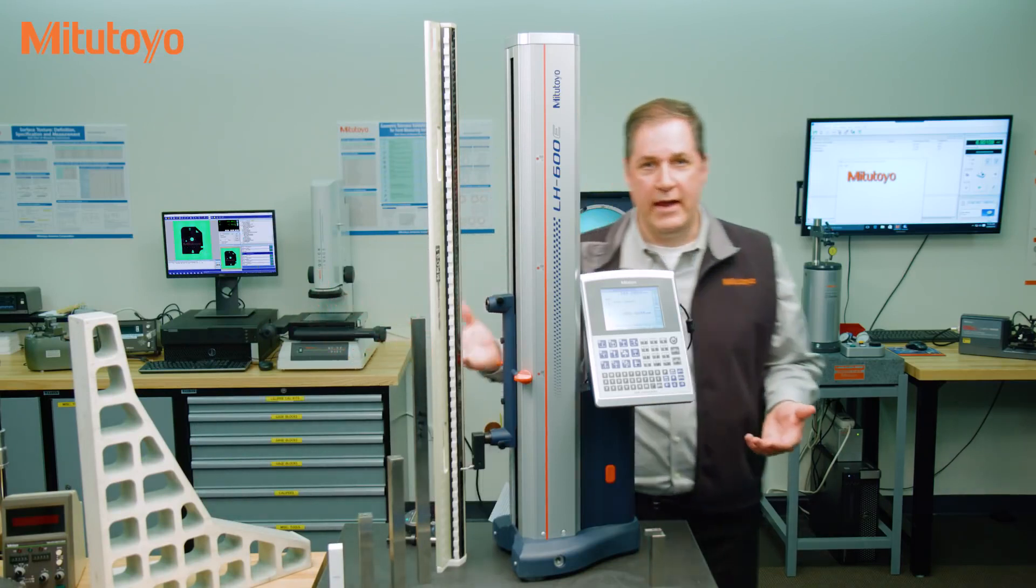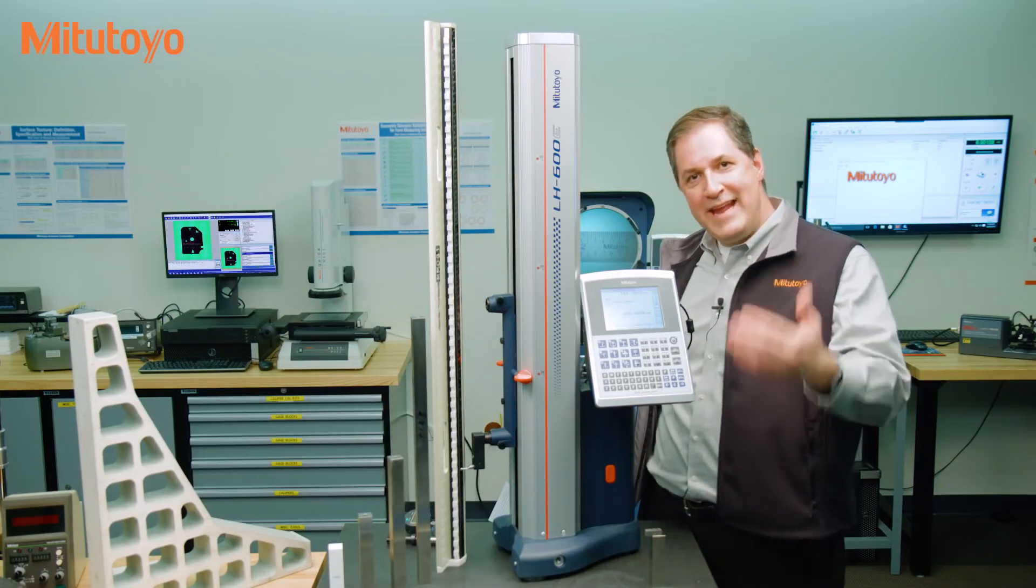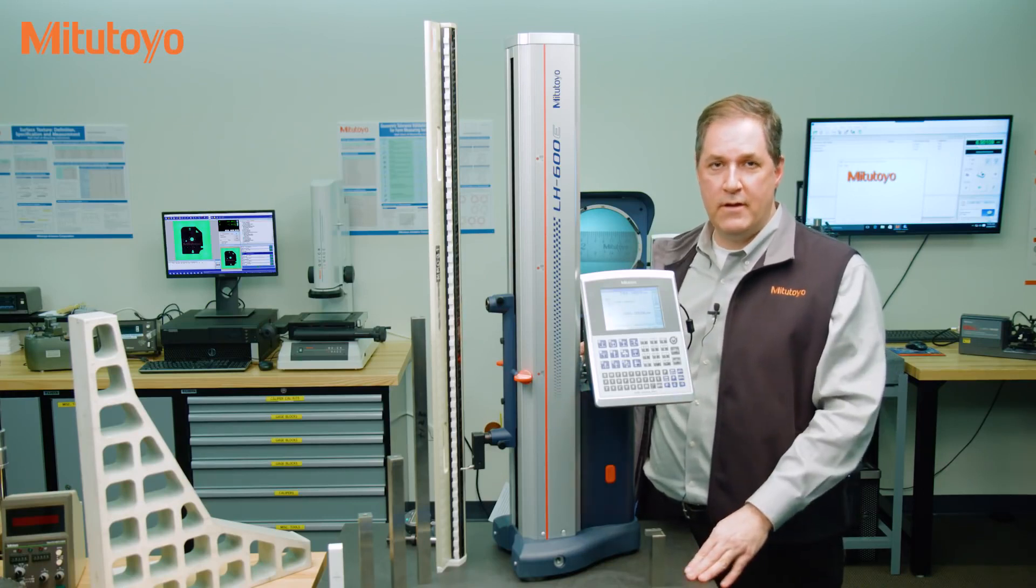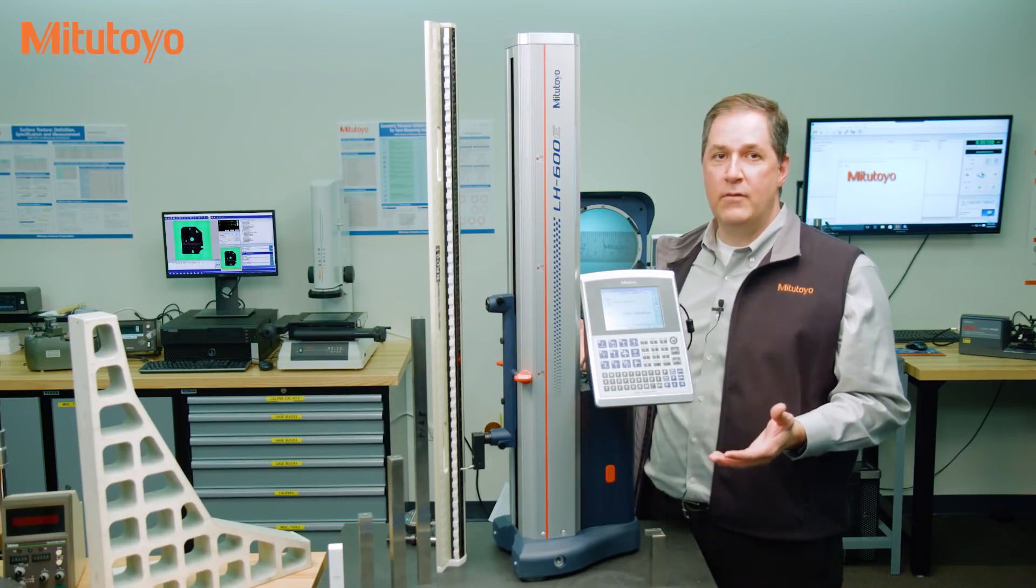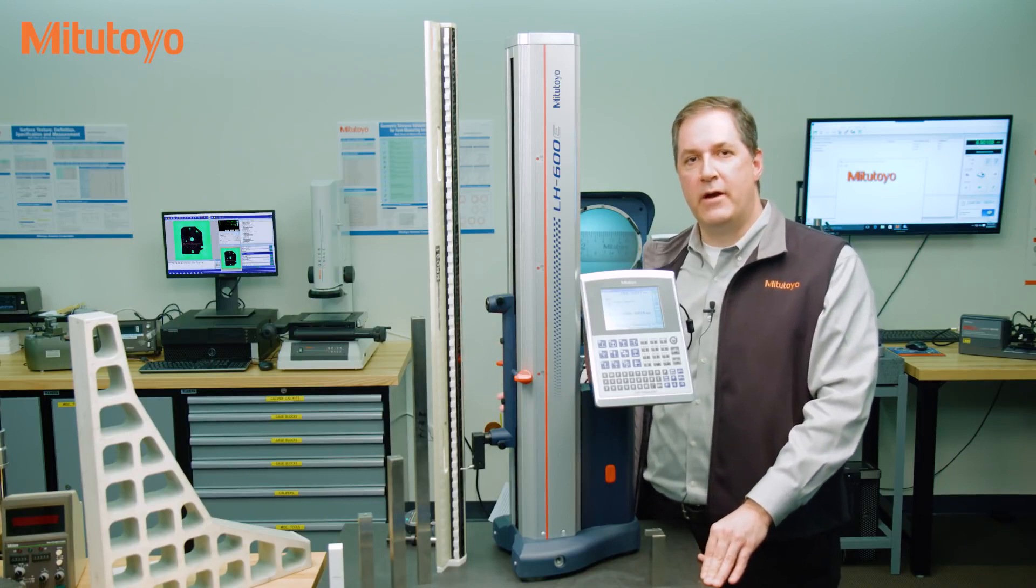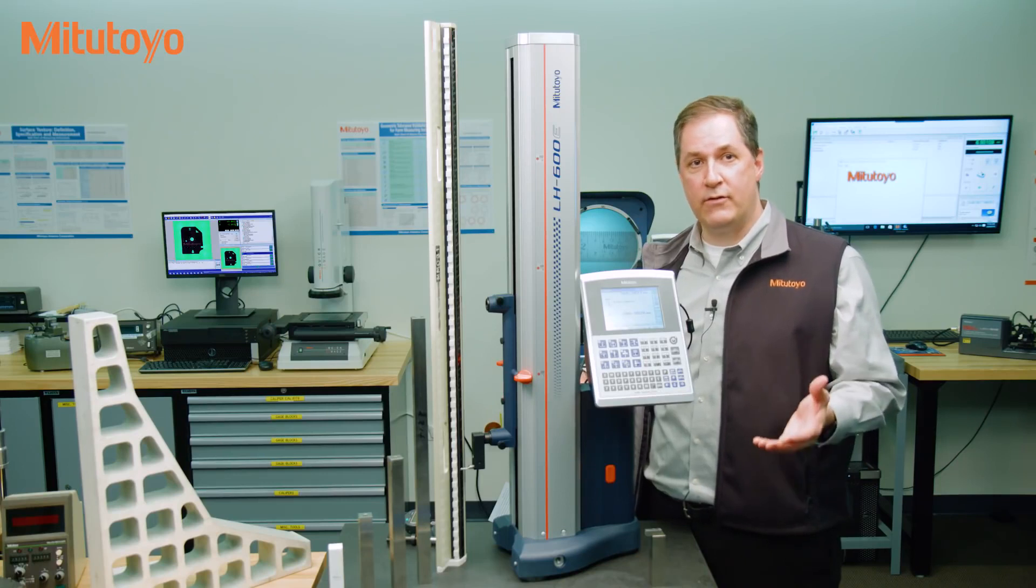So, as the manufacturer of the height gauge, we can give you some advice on the calibration. But the ownership of what needs to be calibrated belongs to you, the user of the measuring equipment. And with today's sophisticated measuring equipment, this is a real problem. Organizations are often not getting the right things calibrated, which can waste money, or even worse, expose your organizations to risks associated with quality.